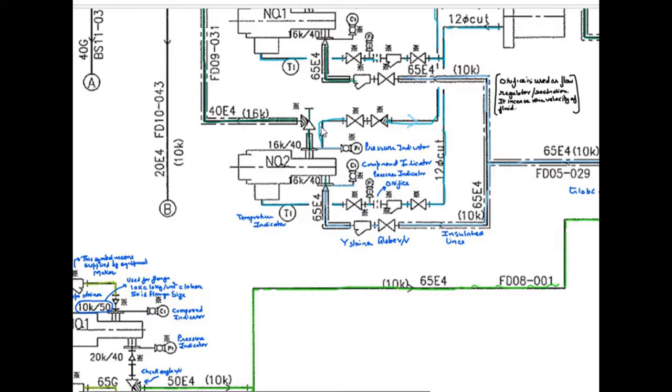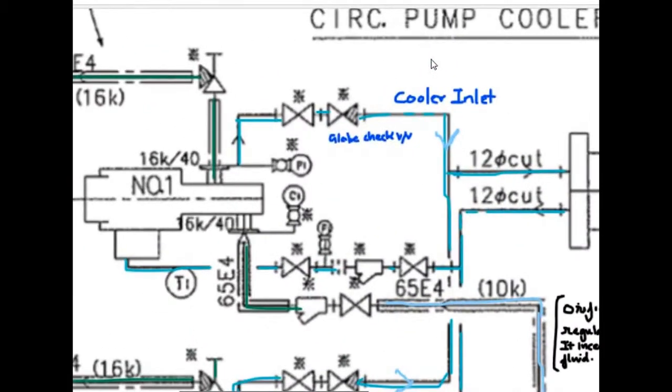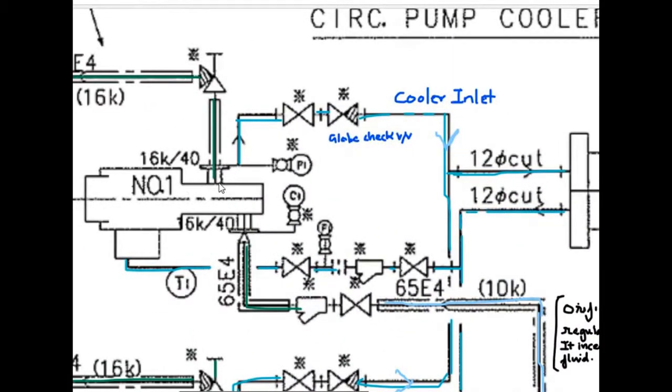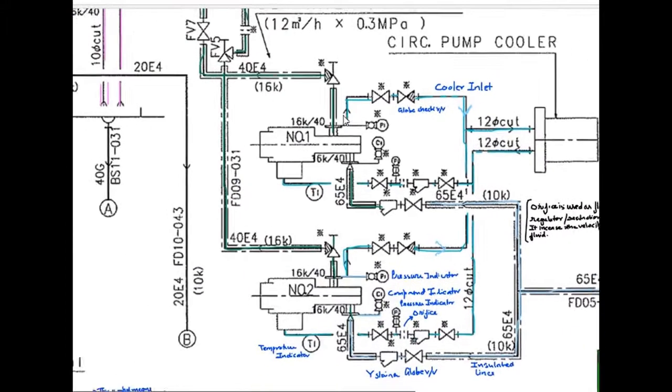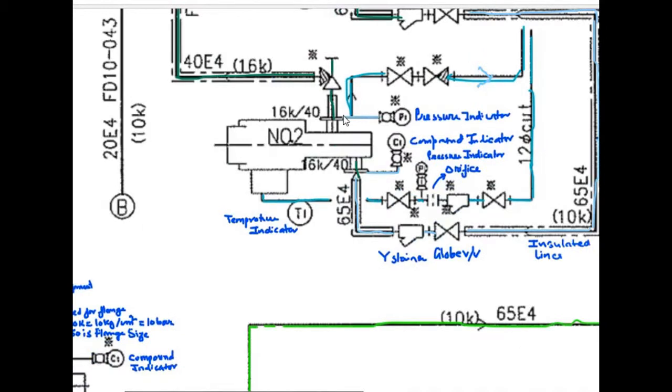One line is going from discharge side to the cooler, and other is coming to the circulating pump. Means, this cooler is cooling the circulating pumps. These two lines are there. You can see in the both pumps, we have globe check valves. Means, the outlet from the pump is going to the cooler through globe check valves. Now, you can see in the suction side, we have temperature indicator. Here, we can see the cooling is effective or not.